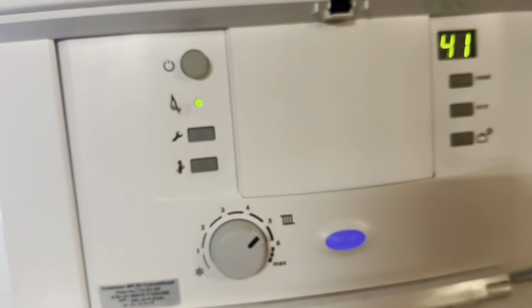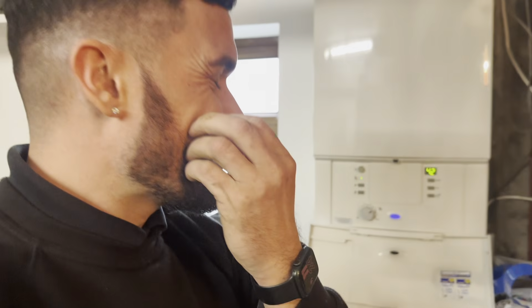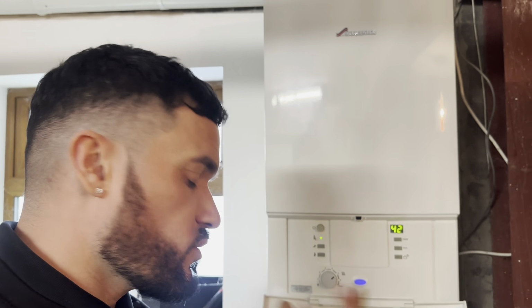So also the return is still stone cold because it's flowing on the system. So once we start getting an equilibrium on the flow and returns, it's an 11-degree differential. I'll have to check manufacturing instructions, but rule of thumb is 11-degree differential - flow out at 80, return at about 69. All works in your thermistor to make sure it's working.